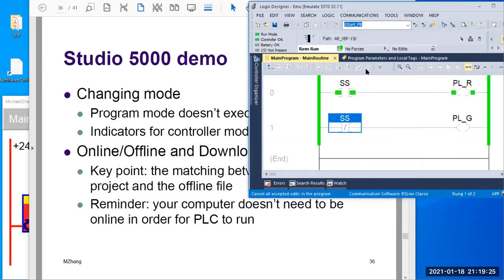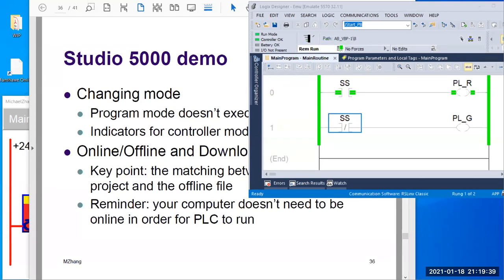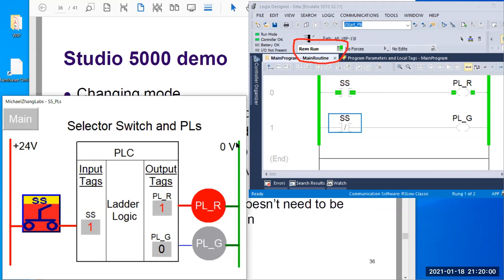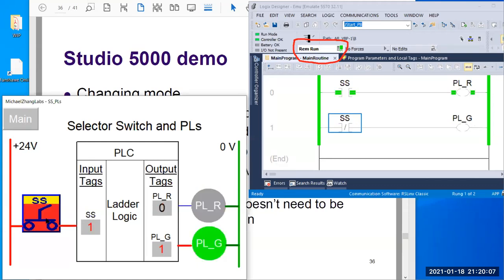First, I want you to pay attention to a very common mistake. People will forget to look at the mode. This is the online toolbar here — this is the indication for your mode. If you forgot about this, you will see some strange things and you won't know what's happening. So for example, this is what you're supposed to see on the HMI and the logic — you can see they are reflecting in direct agreement with the HMI and logic.